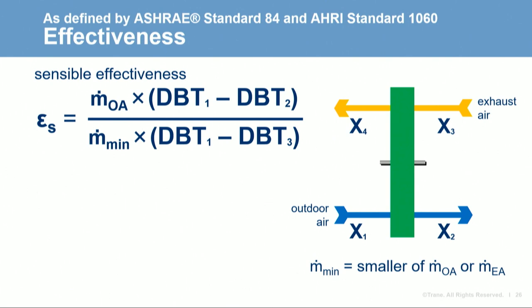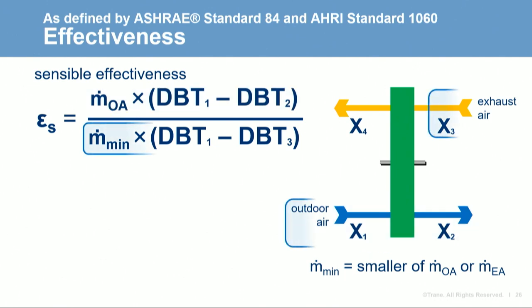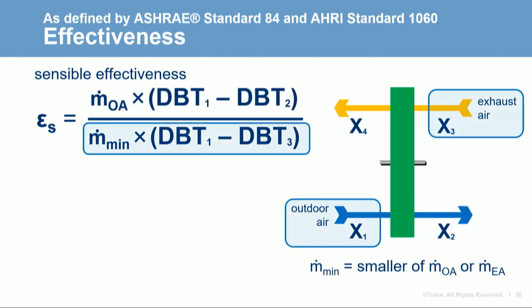Effectiveness is defined as the actual energy transferred divided by the theoretical maximum possible energy transfer between the two airstreams. For sensible effectiveness, the numerator is the mass flow of the outdoor air passing through the supply side of the device times the change in dry bulb temperature from entering to leaving — from location one to location two. The denominator is the maximum possible energy transfer, dictated by the dry bulb temperature of the air entering at location one minus the temperature of the entering exhaust air at location three.